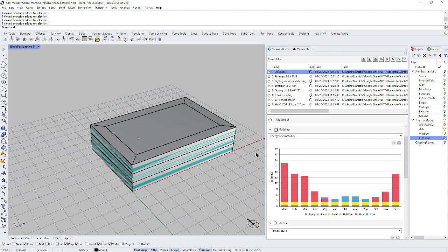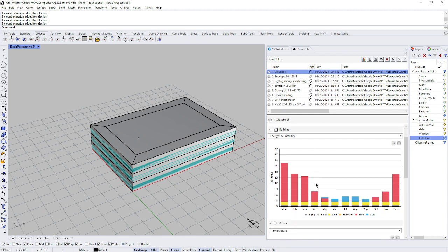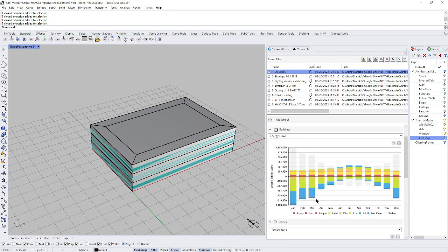Okay, so what we're starting with then, and what I'm calling the old school simulation, is a building. I just tried to make a crappy building. So I gave it a really bad envelope. It's leaky. No thought to it, doesn't have LED lighting, etc. Because I wanted to get something above the baseline, I accomplished that. We see that we've got a lot of heating load, some cooling load. Maybe we can deal with the lighting efficiency some. There's a lot we can do with the envelope, which is in the green. So let's just move from here.